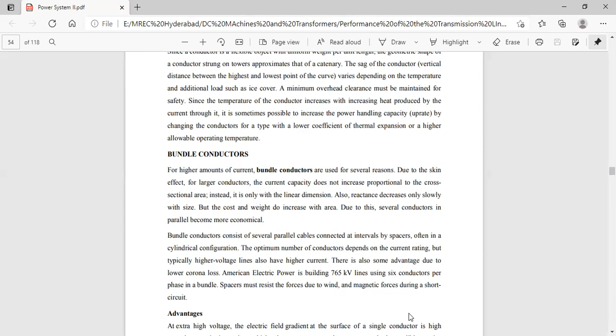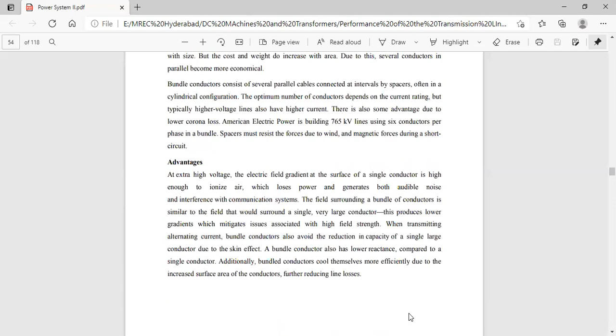The bundle conductor consists of several parallel cables connected at intervals by spacers, often in a cylindrical configuration. The optimum number of conductors depends upon the current rating, but typically high voltage lines also have higher current. There are also some advantages due to lower corona loss. American Electric Power is building a 765 kilovolt line using 6 conductors per phase in a bundle. The spacers must resist the forces due to wind and magnetic forces during short circuits. So these are the advantages of the bundled conductors.